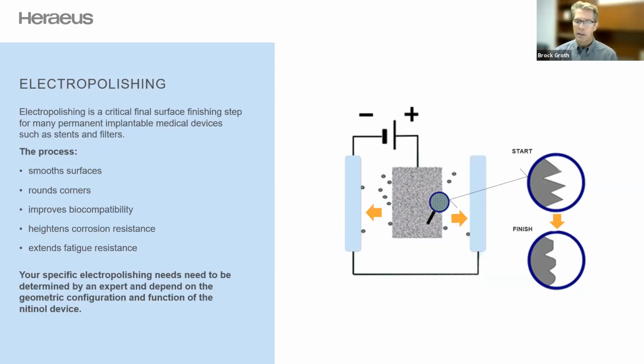The main method for testing corrosion resistance in small implantable medical devices or nickel titanium implantable devices is potentiodynamic corrosion testing, ASTM F2129, and it measures the breakthrough potential. This thin adherent oxide layer will prevent that breakthrough of corrosion and will give you better corrosion resistance. And also, this smoothing will improve your fatigue resistance. Cracking in fatigue is basically crack propagation, and if you have a smoother surface to start with, you will have less opportunity for a crack to start, and then that alone means that your crack propagation is going to be delayed, and electropolishing will improve your fatigue performance.